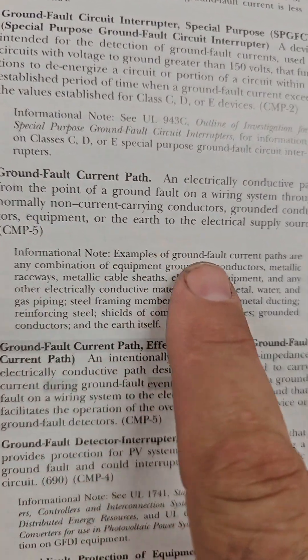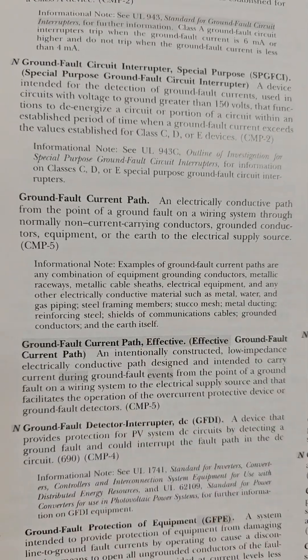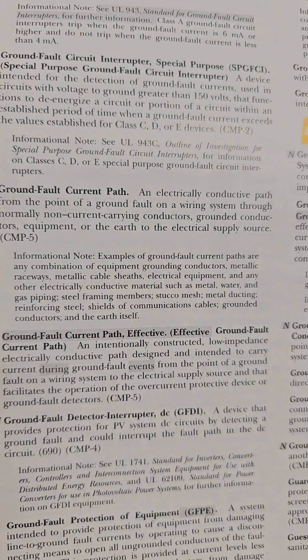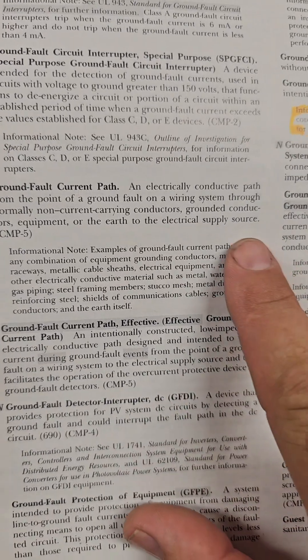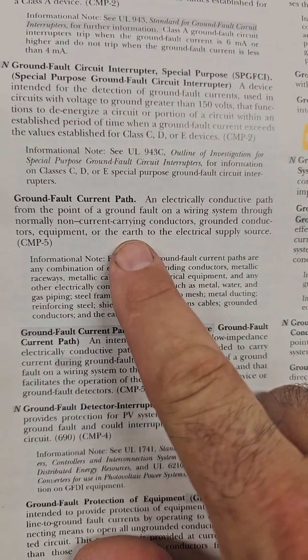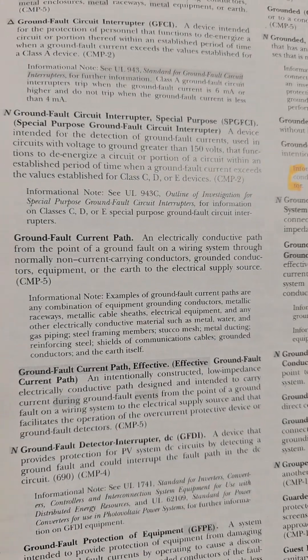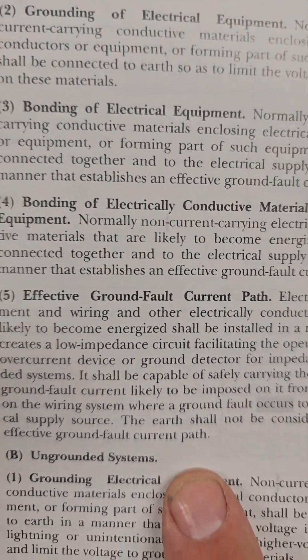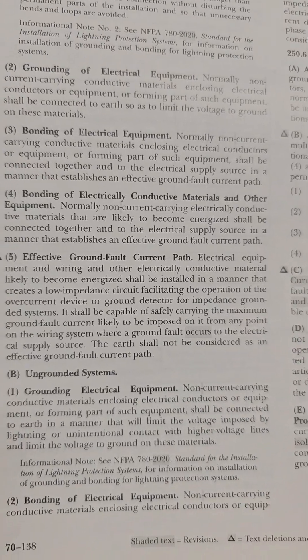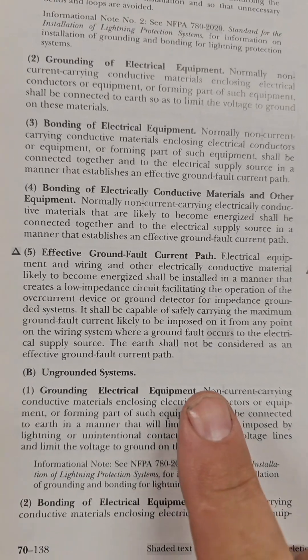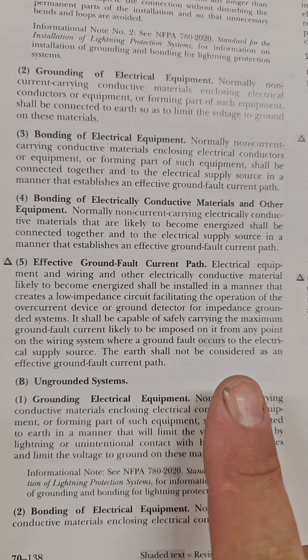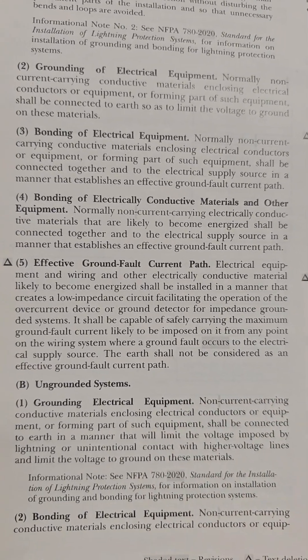But if you go to ground fault path, it does say the earth is in part of the path or could be part of the path. It's still going to the source, but the earth is listed as part of the path. It looks what happens when you go to 250. In 250 grounding and bonding, they talk more about effective ground fault path. And the last line is, the earth shall not be considered as an effective ground fault path.